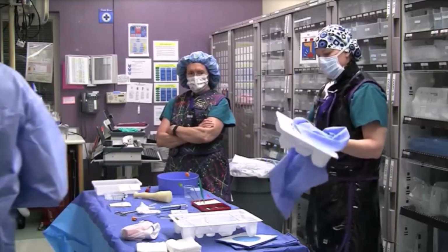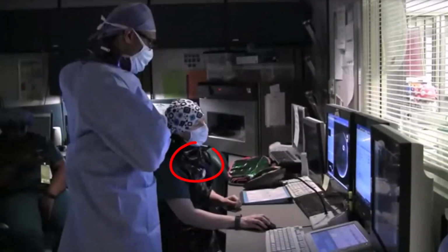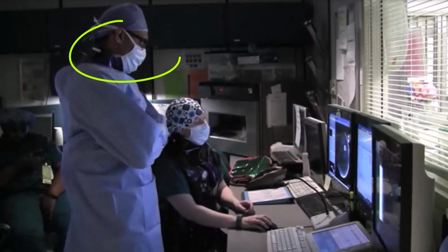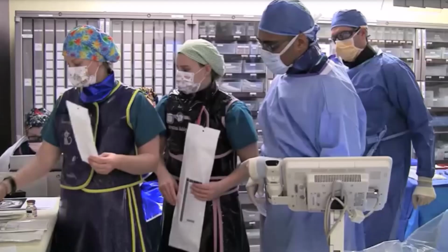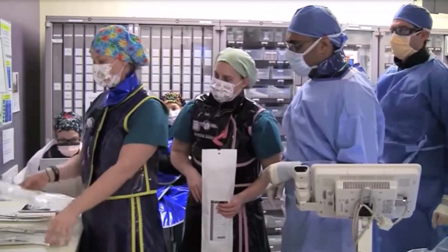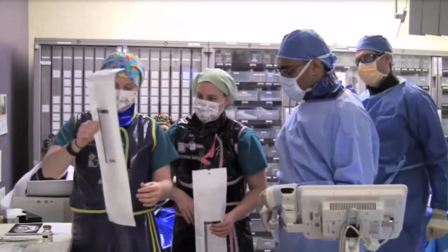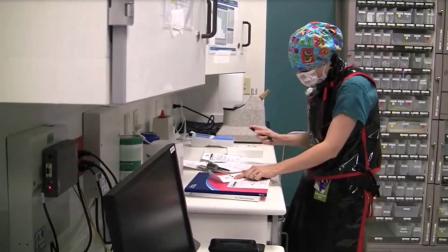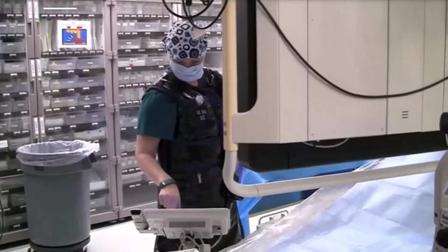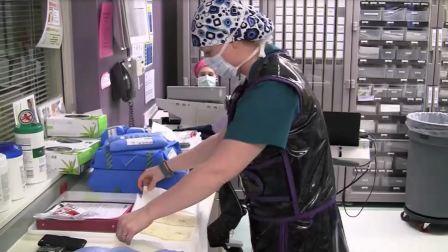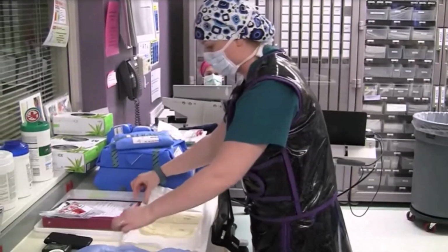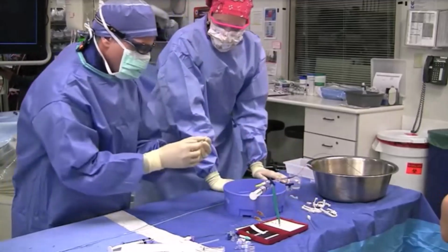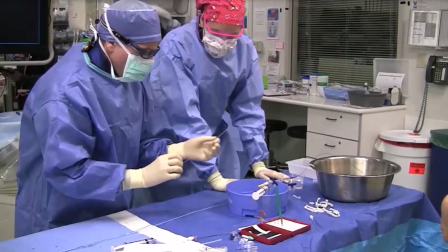Thyroid collars. Use thyroid collars to protect the thyroid gland, which is extremely sensitive to radiation. Lead glasses. Wear lead glasses to protect your eyes from scatter radiation. Protective shields. Utilize protective shields, such as mounted shields or ceiling suspended screens, to provide additional protection. Hand protection. Keep hands out of the primary beam unless unavoidable for clinical reasons. If necessary, use leaded gloves.